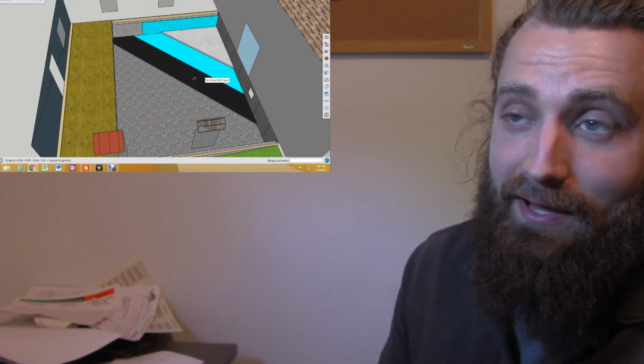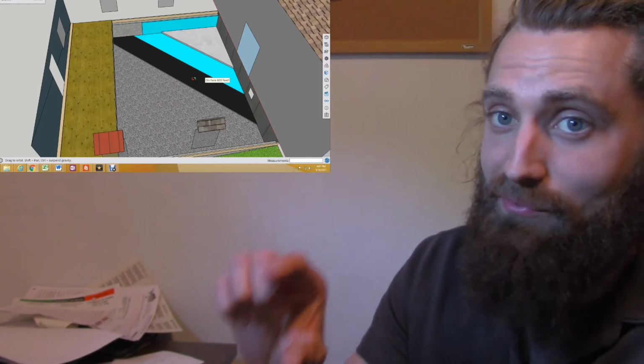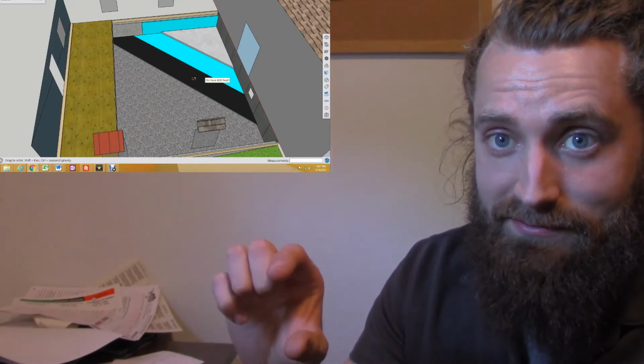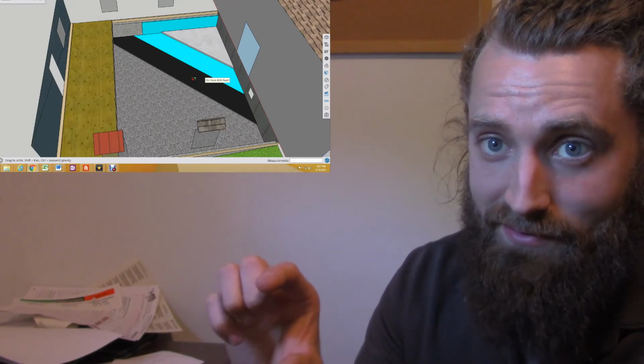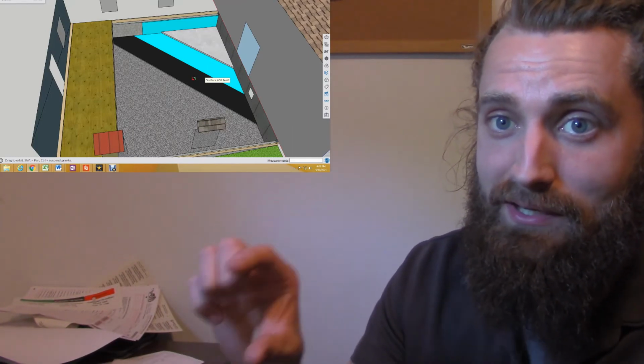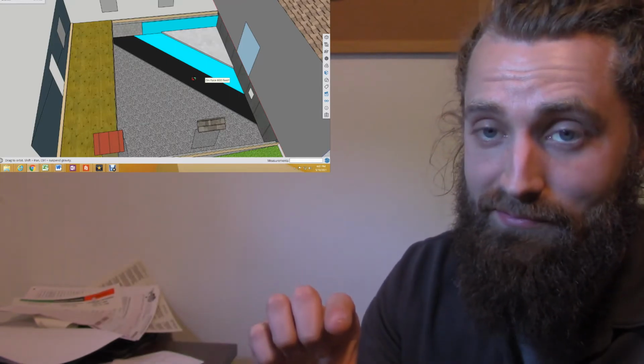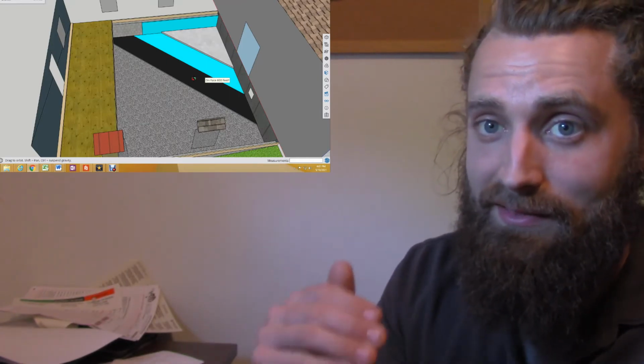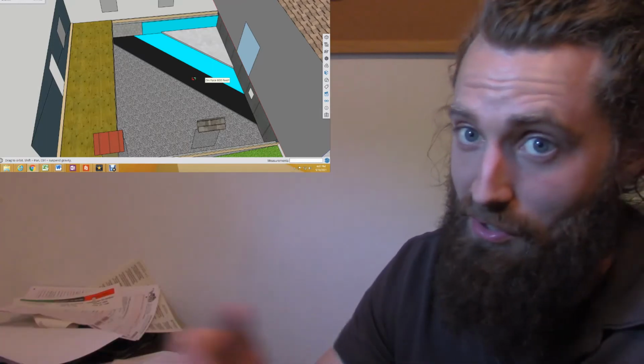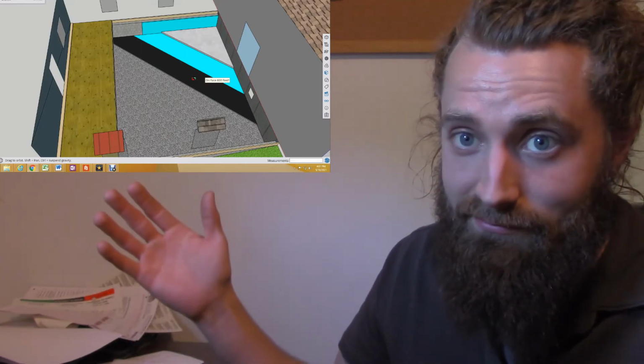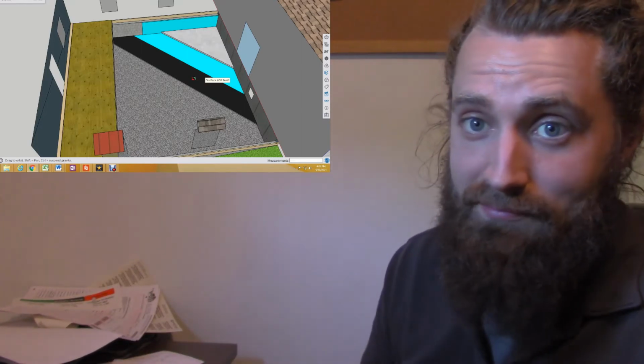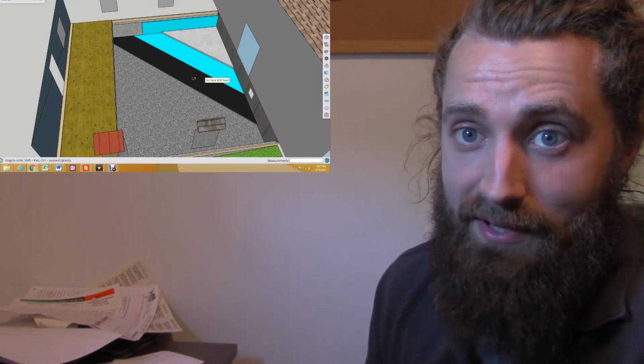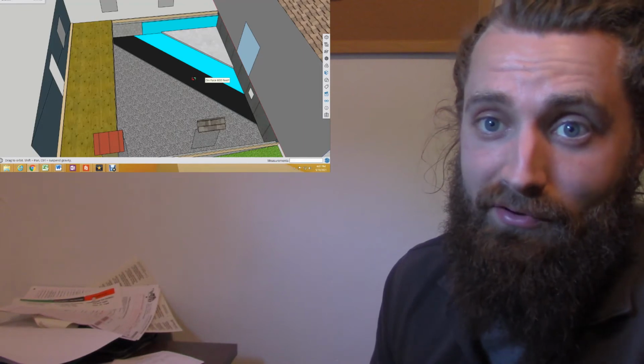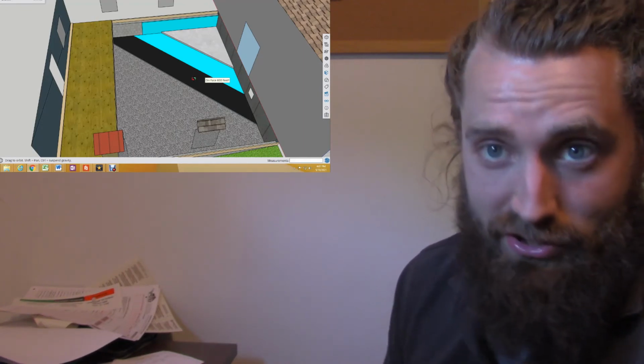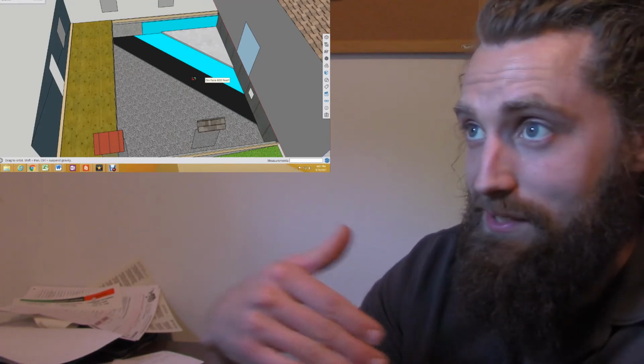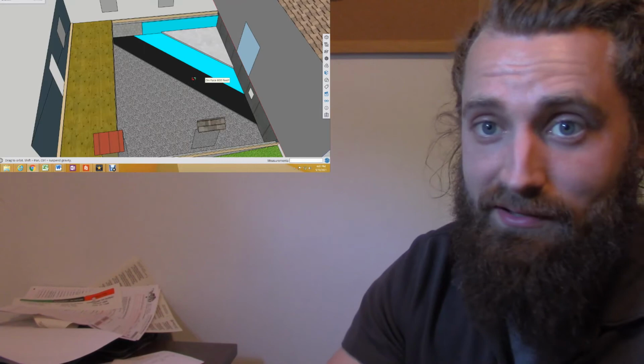That's just the reality of it. We don't know, and that's something you've got to have in the fine print whenever you're looking at a building like this. Yes, according to these blueprints, my site visit, and my load calculations, this is what we need to keep this building comfortable. However, if anything falls outside of this during construction... you see it from time to time where a plumber will come in and hack a hole in the side of the wall for a hose bib, or an electrician will put a receptacle on an exterior wall with no air sealing at all, nothing.